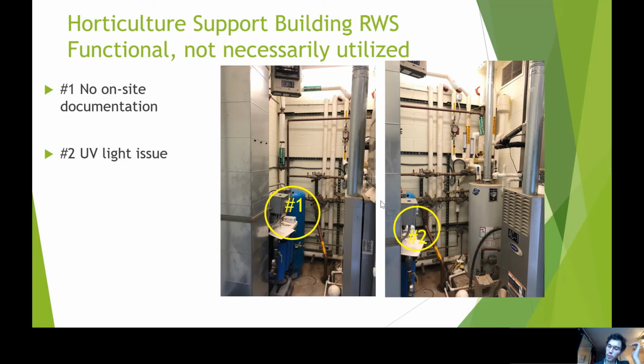And so from its installation in 2010, it was being used for about 5 to 6 years. And then for several years, it was simply off. There's no clear reason as to why, but some of the reasons I think the system was not being used are that there is no on-site documentation, there's no knowledge of the system among the building management people at the botanical gardens where the system is located, and again, a lack of ownership and responsibility for the system. So despite the system working well and being relatively well designed, it hasn't been used.